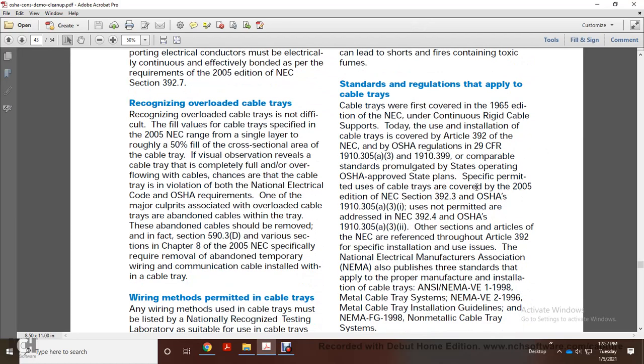Alright, standard regulations apply to cable trays. Cable trays were first covered in the 1965 edition of the National Electrical Code as continuous rigid cable support. The use and installation of cable tray is covered in Article 392 of the National Electrical Code and OSHA Regulation Title 29 CFR 1910.305(a)(3), 1910.399.